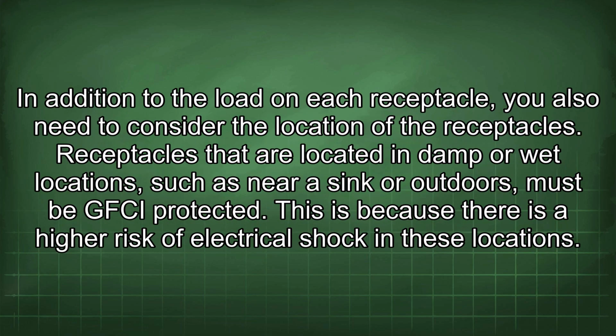In addition to the load on each receptacle, you also need to consider the location of the receptacles. Receptacles that are located in damp or wet locations, such as near a sink or outdoors, must be GFCI protected. This is because there is a higher risk of electrical shock in these locations.